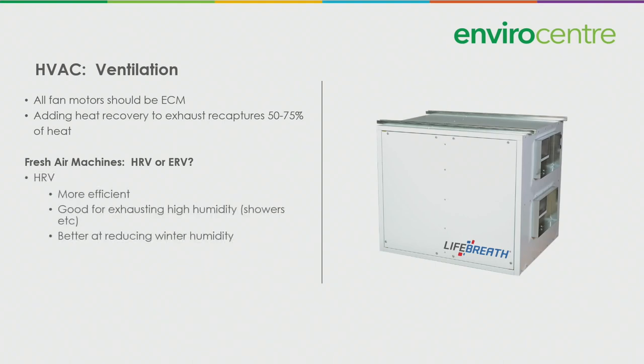HRVs are, as compared to ERVs, more efficient. They're good for exhausting high humidity zones like showers, places where there are showers, etc., or maybe a lot of boiling water, a lot of steam. They're better at reducing winter humidity. So if that's what you want to do, that's maybe the direction you should go.